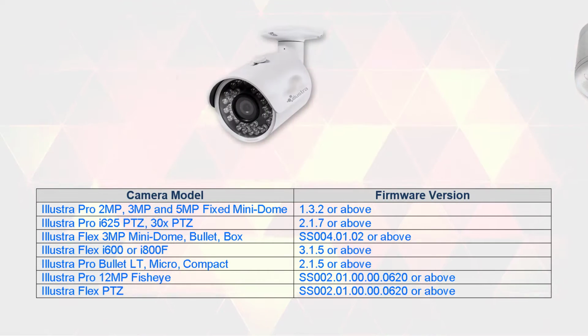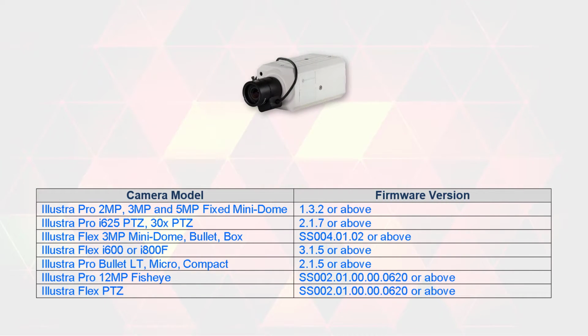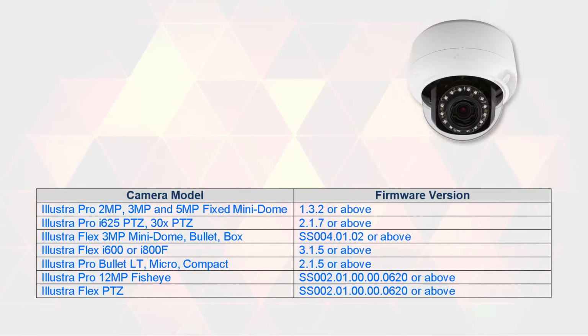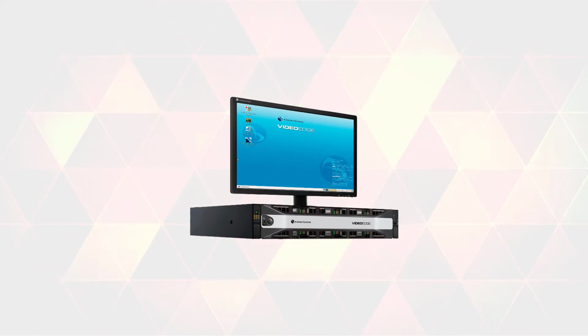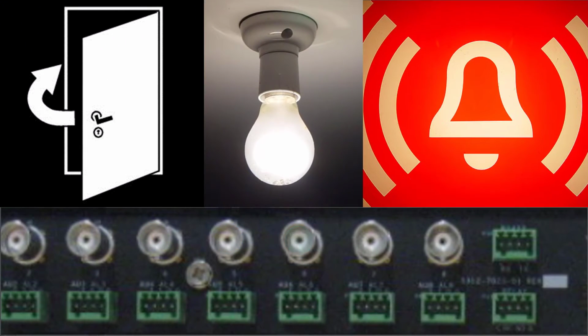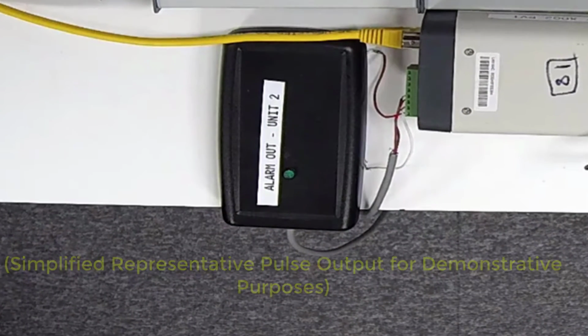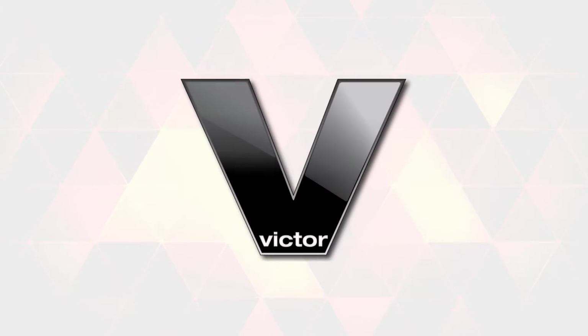The digital inputs on the interfaces can be wired to devices which, when triggered, generate alerts on the NVR. Moreover, the outputs can be wired to a relay in order to trigger an external device, such as a door magnet, a light or a buzzer, to activate or deactivate. Pulse functionality is also available. Any such external device so connected can also be triggered or pulsed from American Dynamics Victor Client, version 5.1 and above.